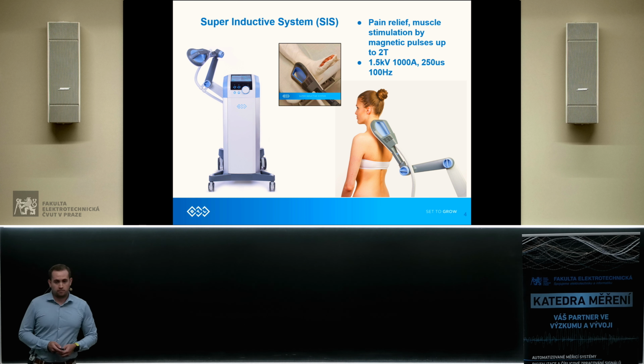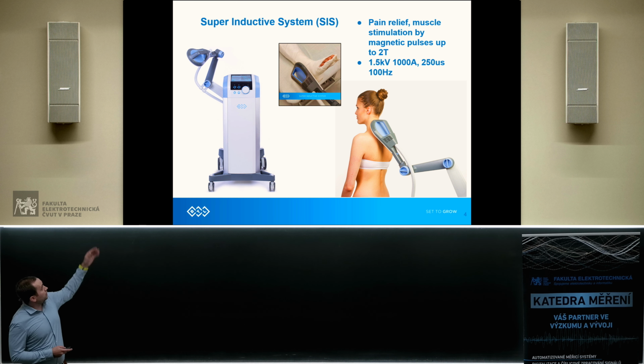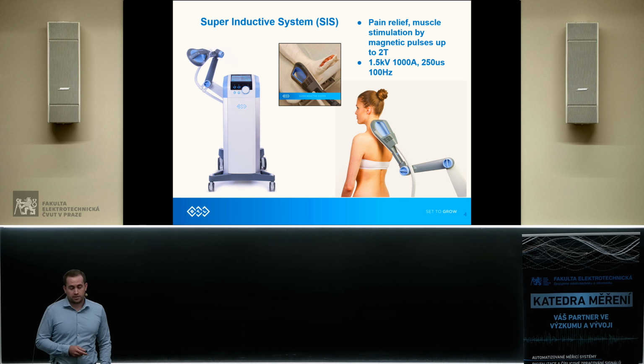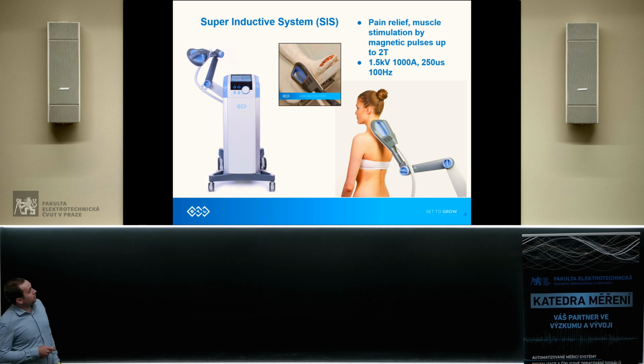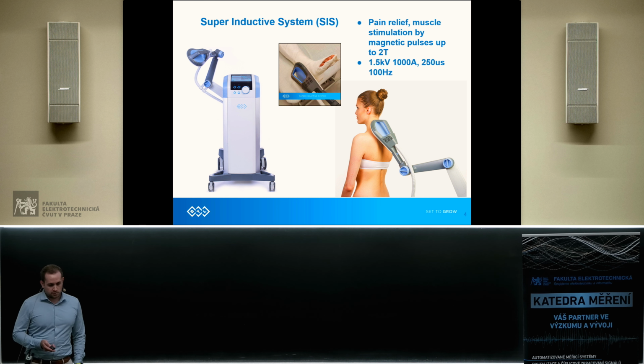The first one is typical of our devices: they are in such a box, a white box. This one particularly does some magnetic stimulation. So this is the device itself. It has some kind of applicator. And this one particularly does 2 Tesla pulses. It helps with chronic pain, for example, some muscle relief. So it's a big magnetic field. It means we should shoot into the applicator with 1.5 kilovolts, 1,000 amps in 250 microseconds. So it's a massive energy we deal with.